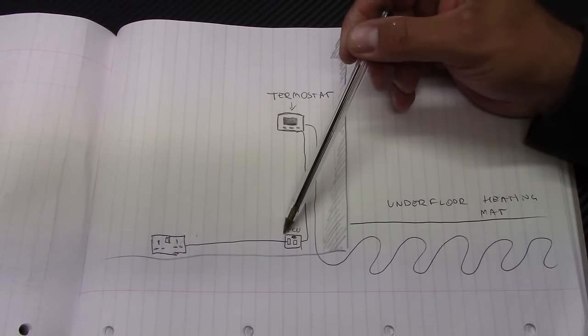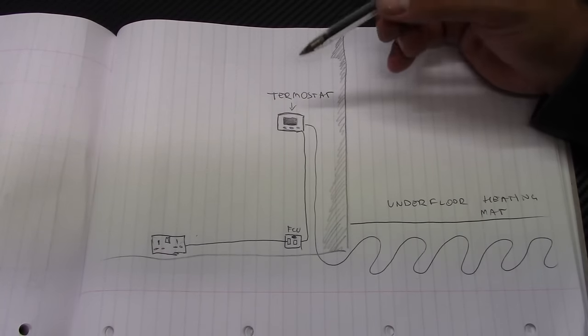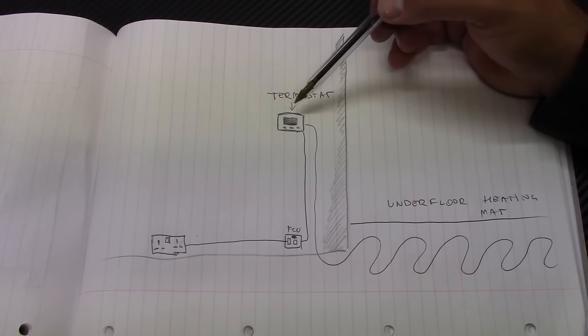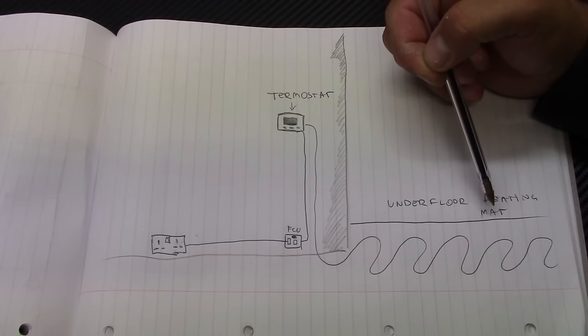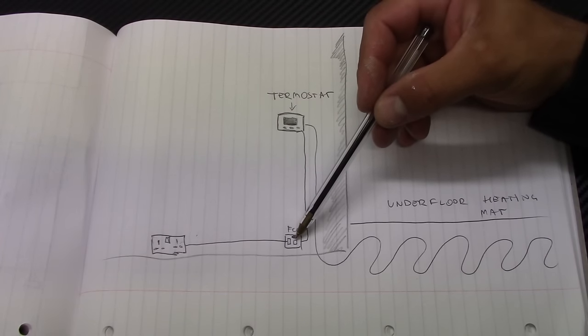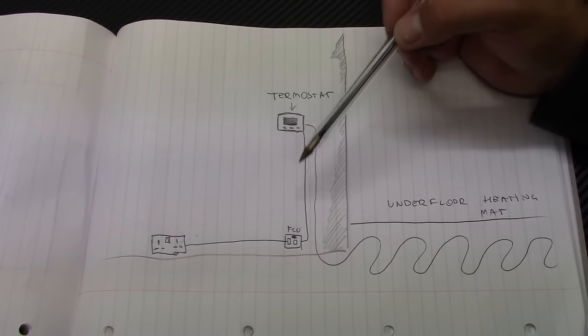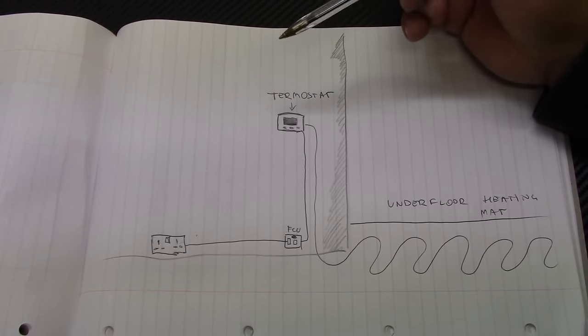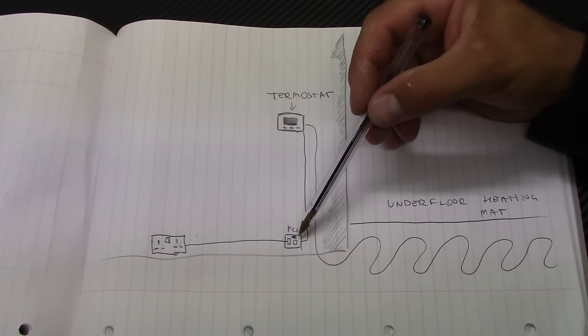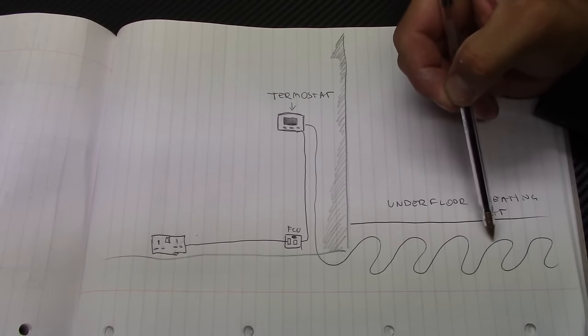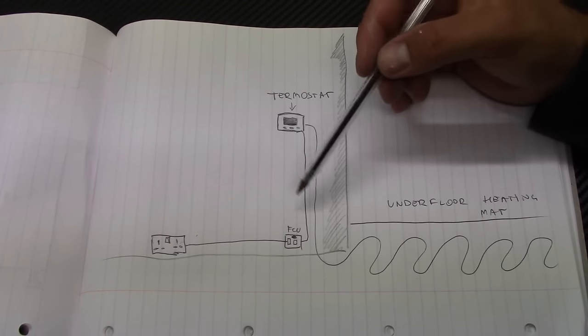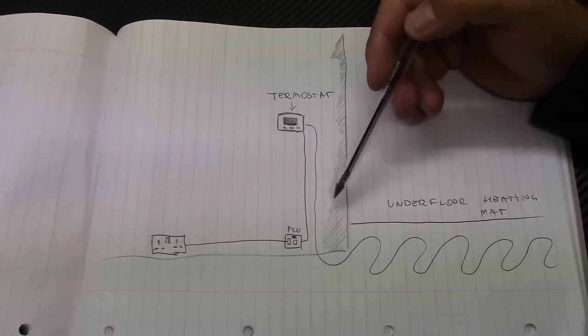So when you take the power from the socket outlet you install FCU, 13 amp FCU just below the thermostat. And this in the future if you need to maintain the thermostat or something happened to underfloor heating mat, you can easily switch it off in here using the FCU switch. Also you need to remember that the load of the mat is limited by the 13 amp fuse here. So the underfloor heating mat cannot exceed 13 amps.